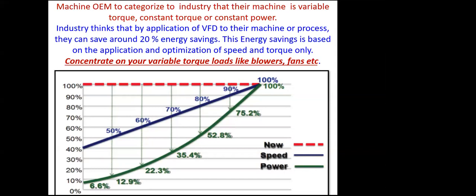It's a backward curve or a forward curve, wherever the fan is, but if it is a centrifugal type, the amount of savings is enormous, provided you are able to optimally fix your speed. Instead of 1500 or 1470 RPM for a given motor, it need not run your blower at 750 RPM.